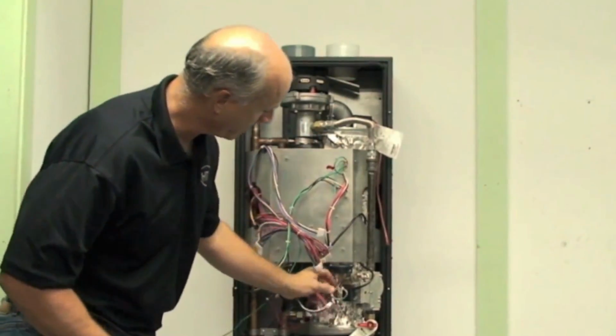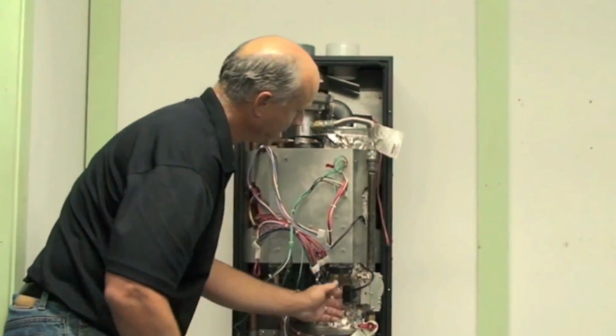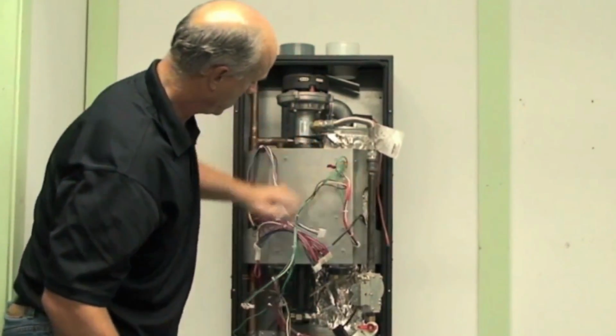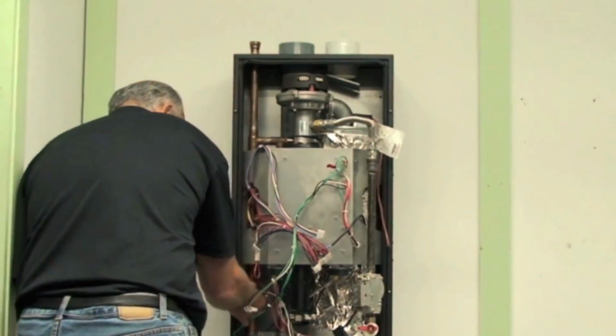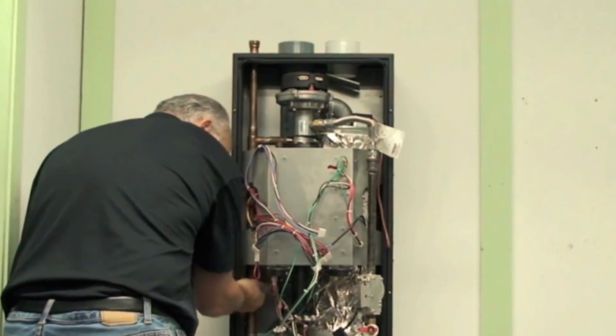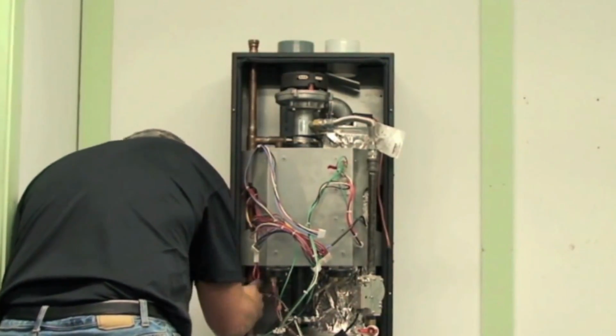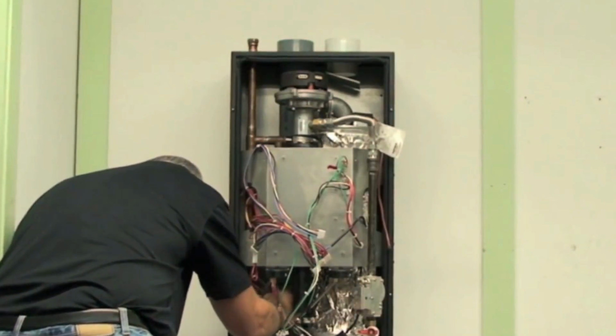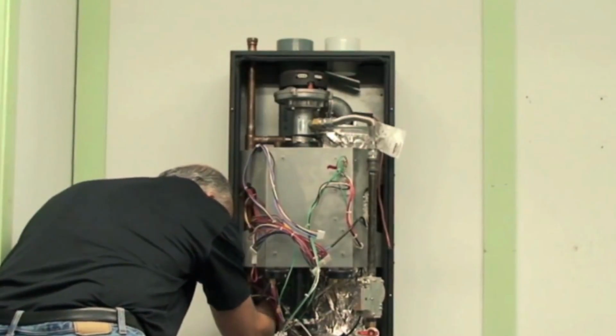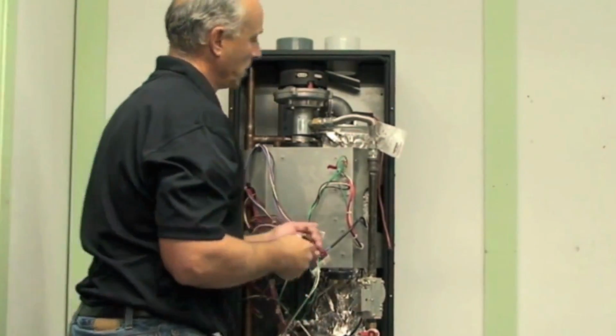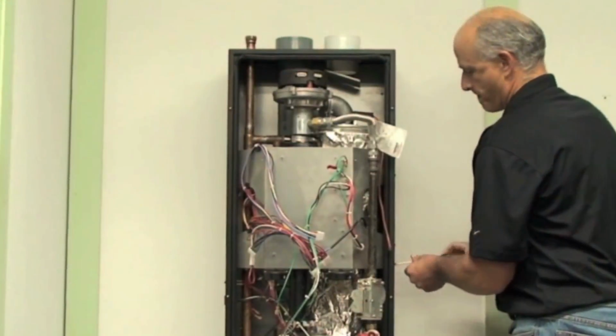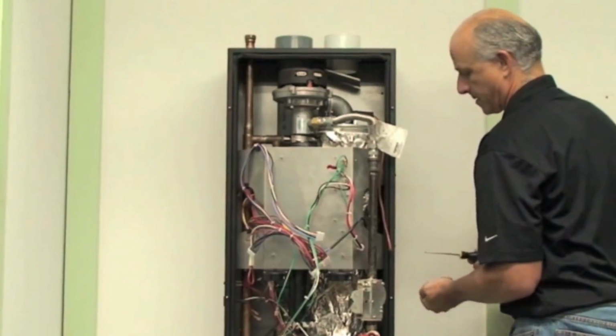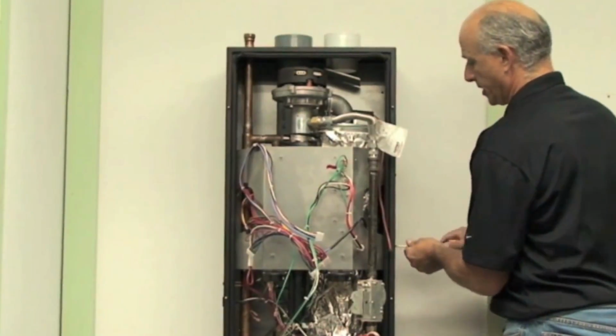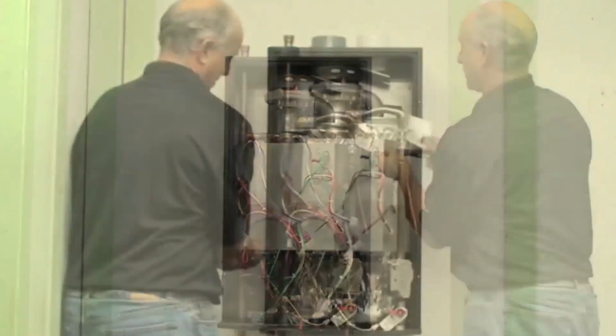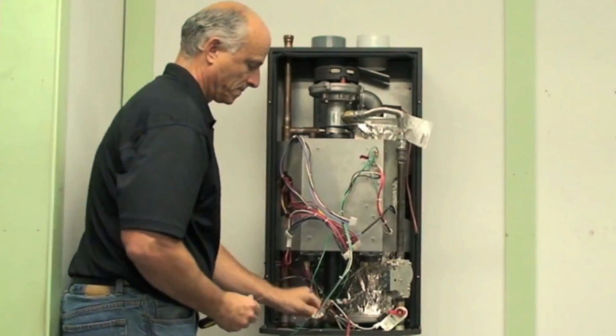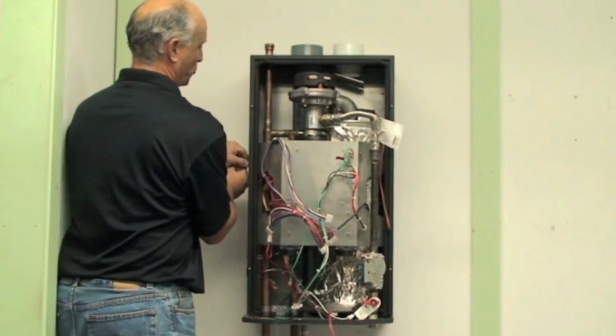Okay, and then I'm going to look down here. This is my block vent switch. Terminals I'm going to take off, my gas valve terminal. And then I'm going to do some disconnecting down here where I'm going to look for some other lines that go up to the control circuit. Right now, the only other ones are my vent switch and my ECO limit for the flue. So now I'm going to disconnect this, which is the bracket. Again, black in color, so they're easy to find. One more screw I got to take out.